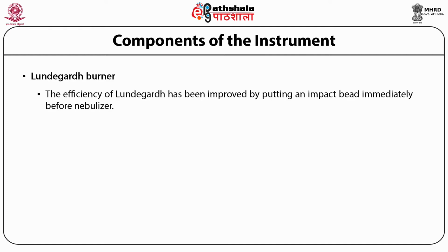The efficiency of the Lundegardh burner has been improved by putting an impact bead immediately before the nebulizer. This impact bead has the effect of breaking up large droplets as they emerge from the nebulizer, thereby increasing the number of small droplets and consequently the efficiency of nebulization.